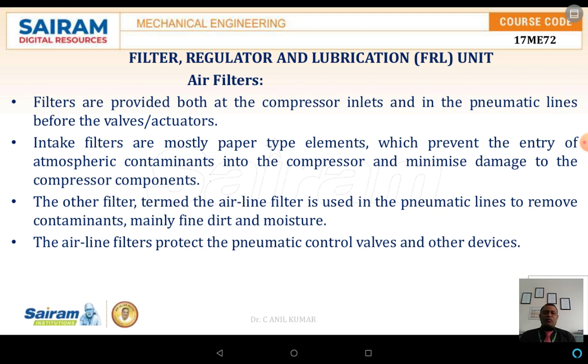The intake filters are mostly a paper type or elements which prevents the entry of atmospheric contaminants into the compressor and minimizing the damage to the compressor components. The other filter, termed as an airline filter, is used in the pneumatic line which removes contaminants, mainly the dirt and also the moisture. The airline filters protect the pneumatic control valve and other devices from corrosion.